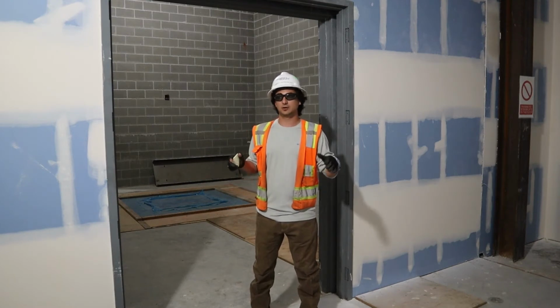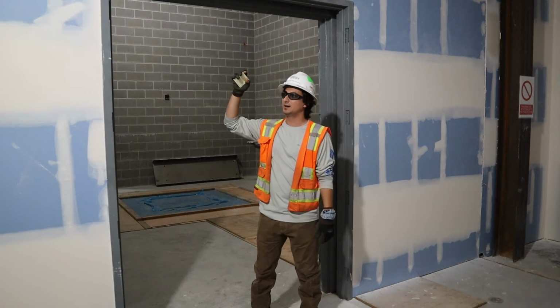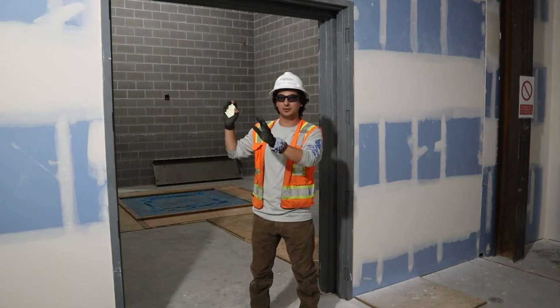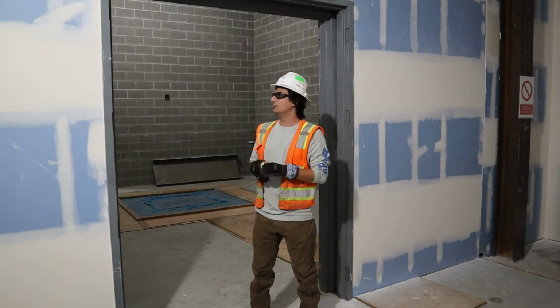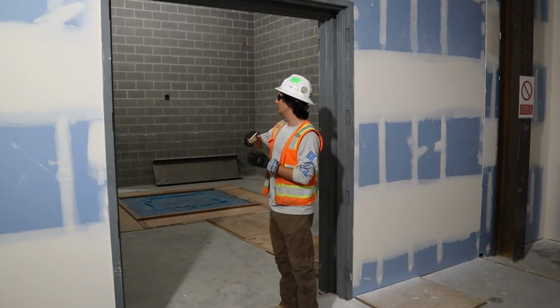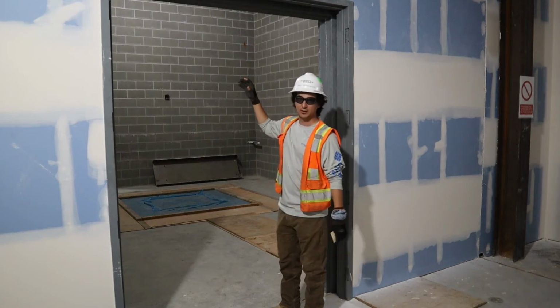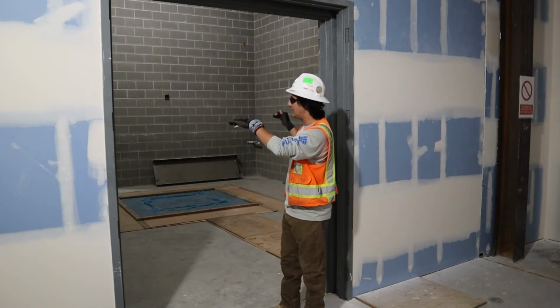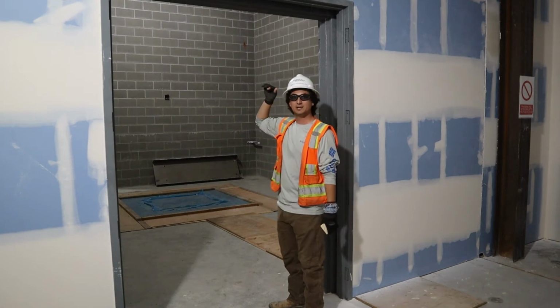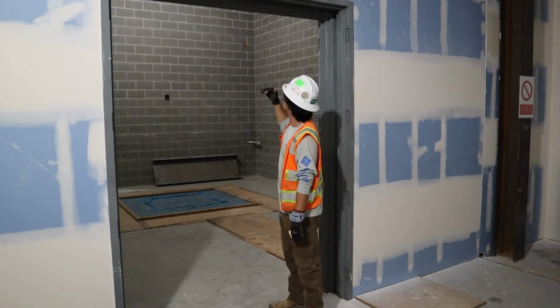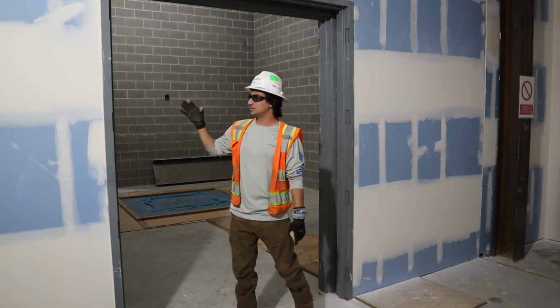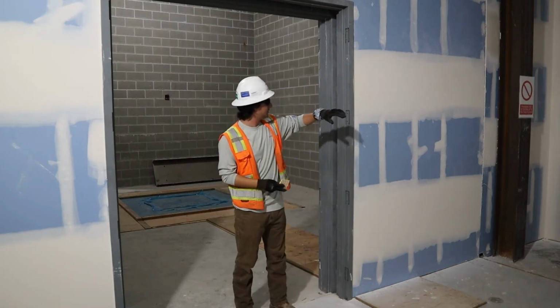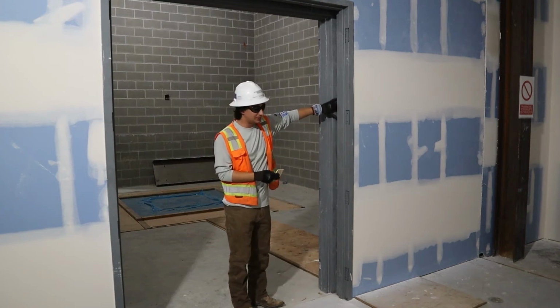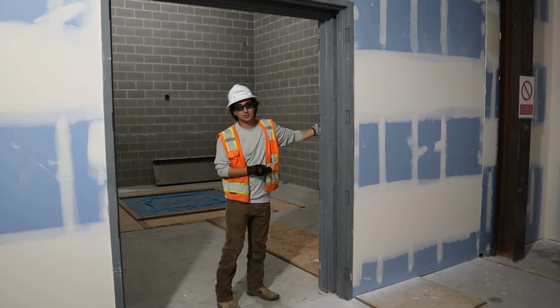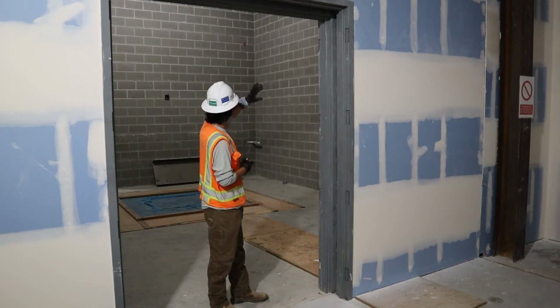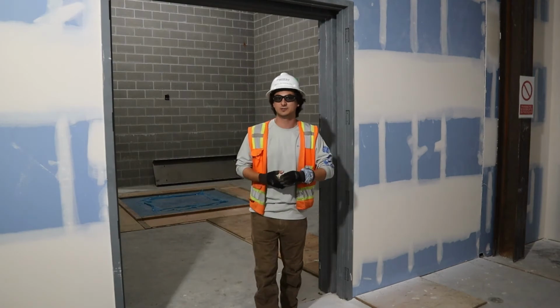On top of it is a structural steel structure, corrugated metal roof deck. Again, completely separate from the adjacent lab building, separated by seismic joints. Inside of that steel and concrete shell are 4 CMU lab cells. They're just freestanding large cubes on top of the slab on grade, and they're capped with a cast in place concrete lid. Each cube is lined on the outside with acoustically absorbent gyp, 6-inch walls, again, completely separated from the lab cell. And on the inside, at some point, we're going to put acoustic wall panels in here to absorb voices and vibrations and stuff like that.